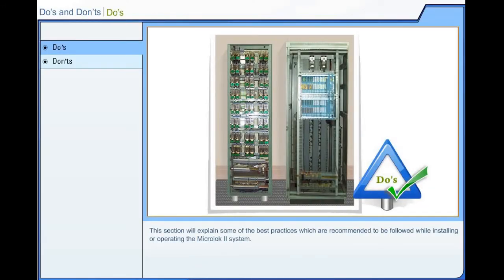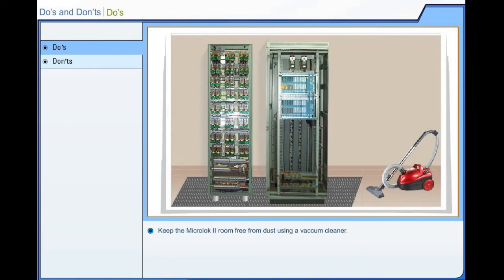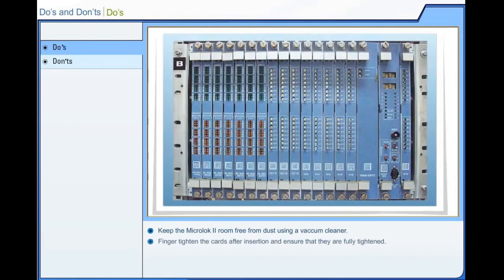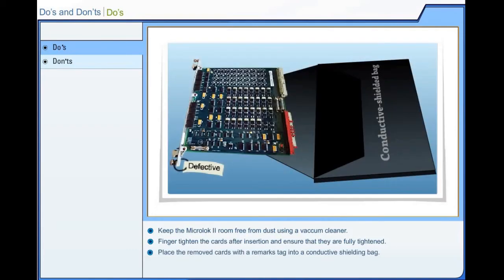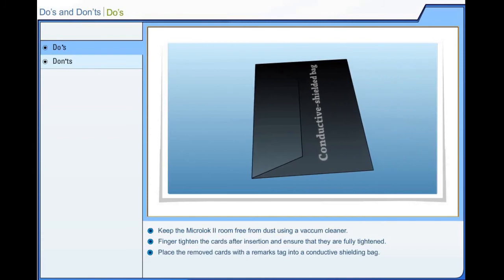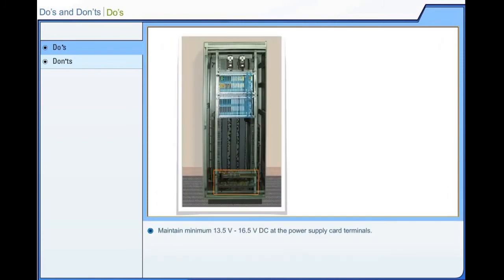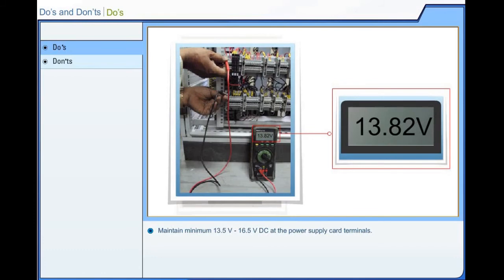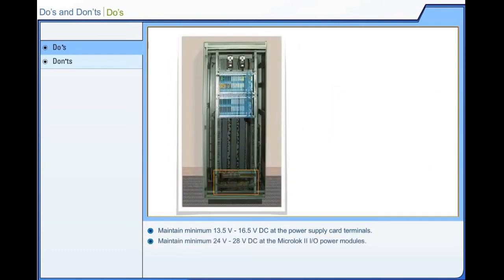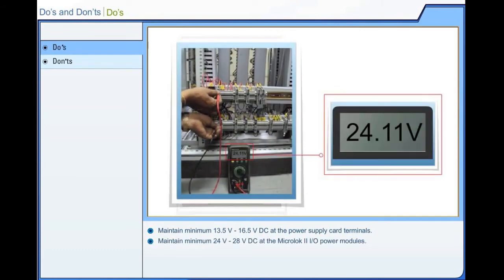Do's and don'ts. Do's. This section explains some of the best practices recommended while installing or operating the Microlok II system. Keep the Microlok II room free from dust using a vacuum cleaner. Finger tighten the cards after insertion and ensure they are fully tightened. Place the removed cards with a remarks tag into a conductive shielding bag. Maintain minimum 13.5 volts to 16.5 volts DC at the power supply card terminals. Maintain minimum 24 volts to 28 volts DC at the Microlok II input or output power modules.